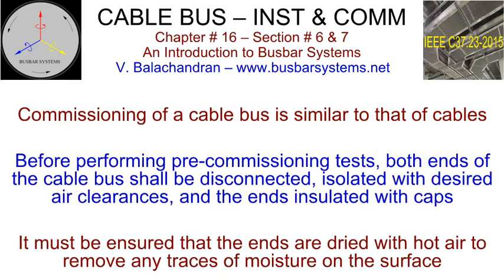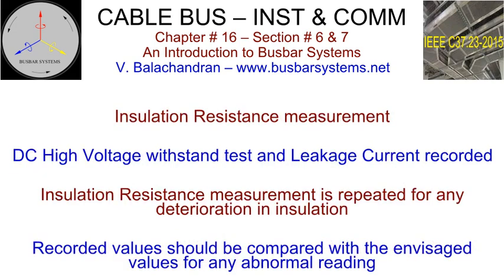Before performing pre-commissioning tests, both ends of the cable bus shall be disconnected, isolated with desired air clearances, and the ends insulated with caps. It must be ensured that the ends are dried with hot air to remove any traces of moisture on the surface. The insulation resistance measurement test is to be performed with an appropriately voltage-rated instrument on individual cables. Conductors of the other cables shall be earthed. The steady-state value of the insulation resistance shall be recorded after the capacitance of the cable is fully charged by the measuring instrument. DC high voltage withstand test is performed by connecting all the parallel paths of the phase under test and earthing other phase conductors along with the enclosure.